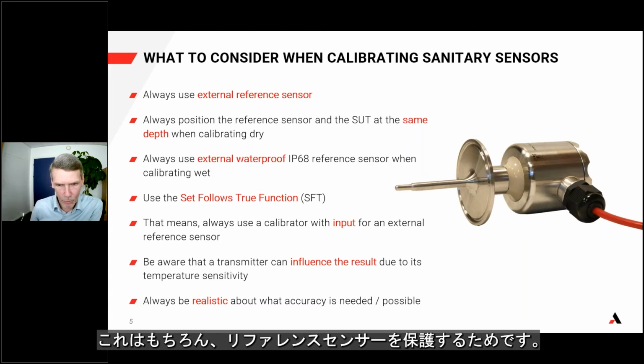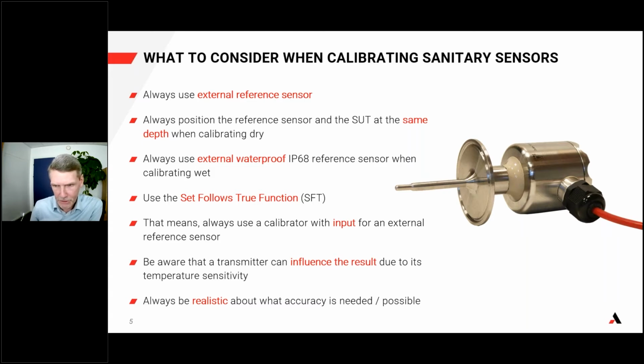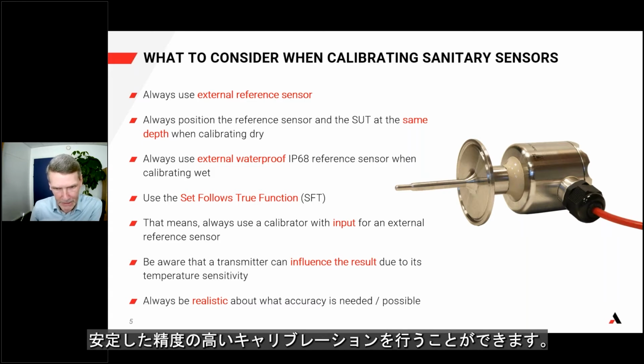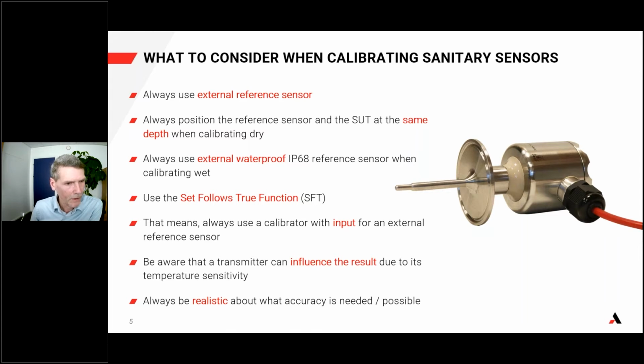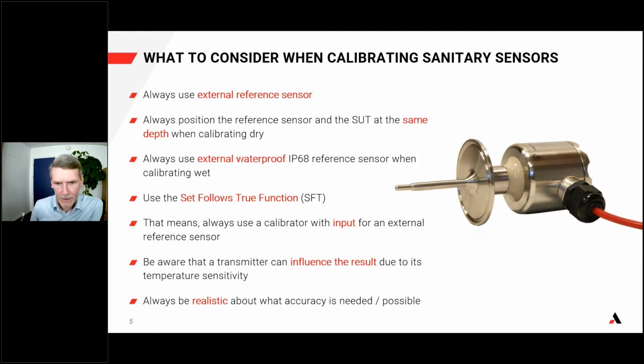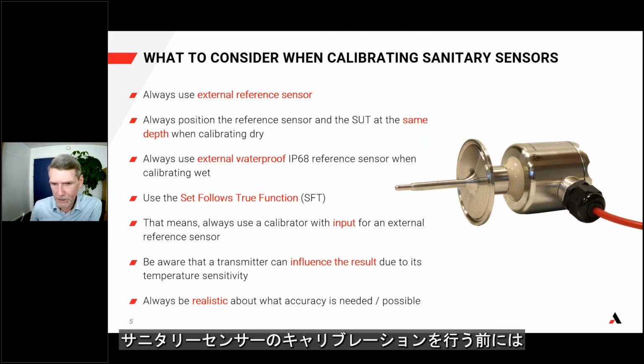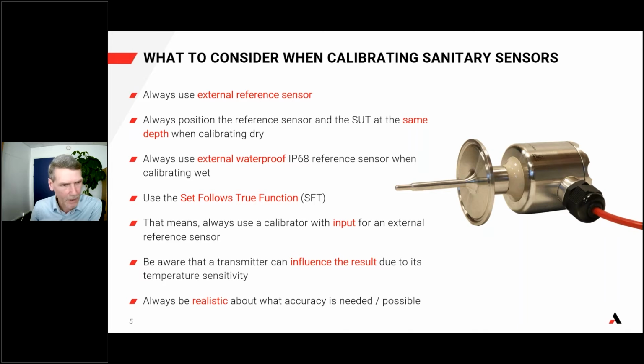Always use an external waterproof IP68 reference sensor when calibrating wet. That is, of course, in order to protect the reference sensor so we can calibrate with stability and accuracy. Use the set follows true function. The set follows true shall always be activated when performing sanitary sensor calibration.